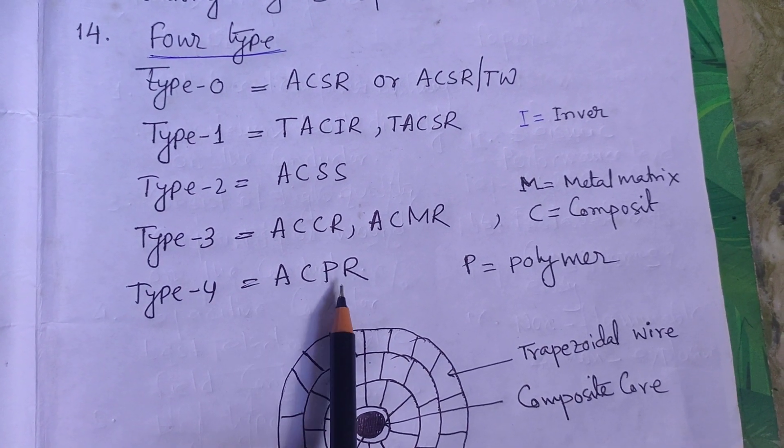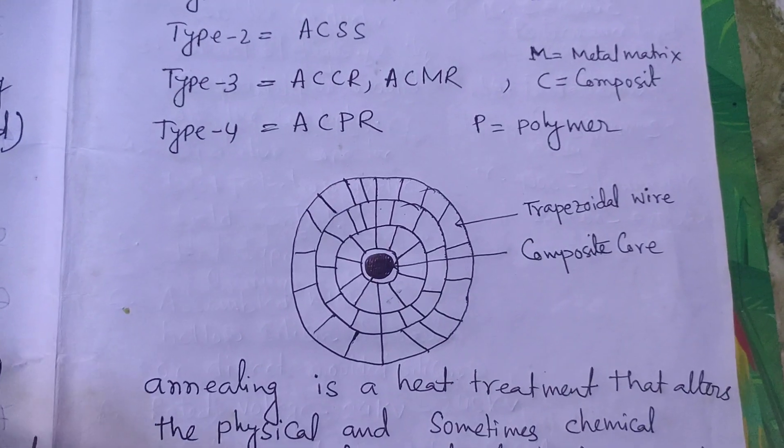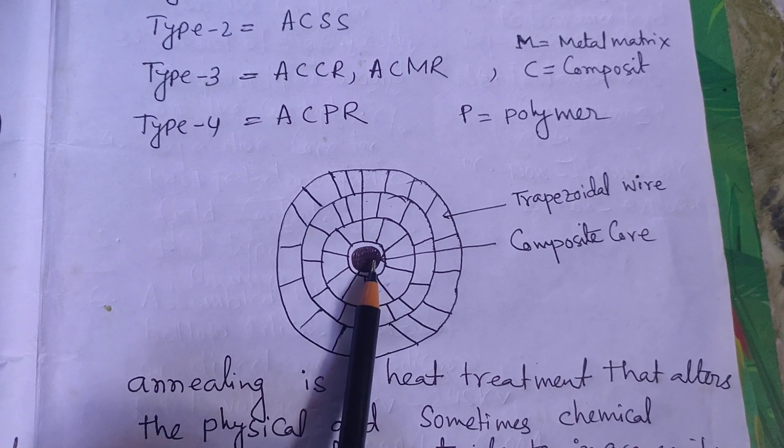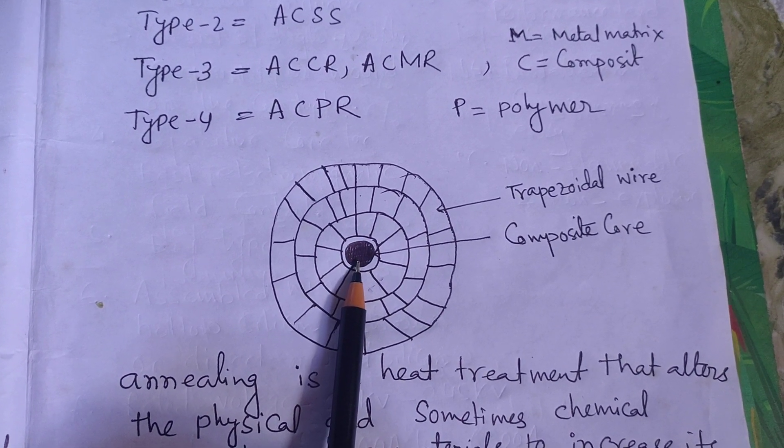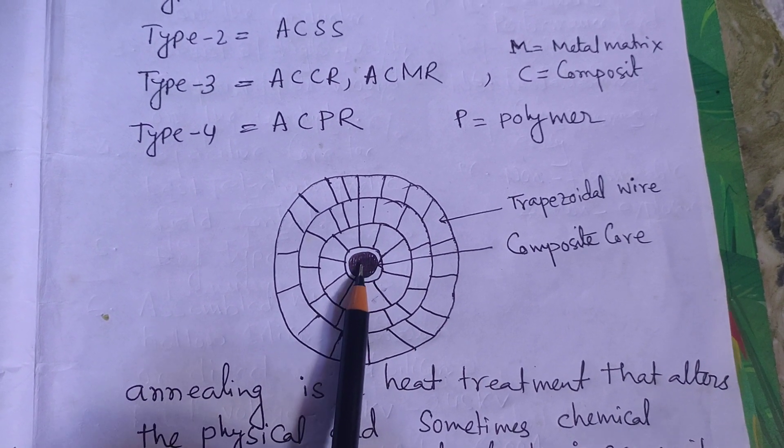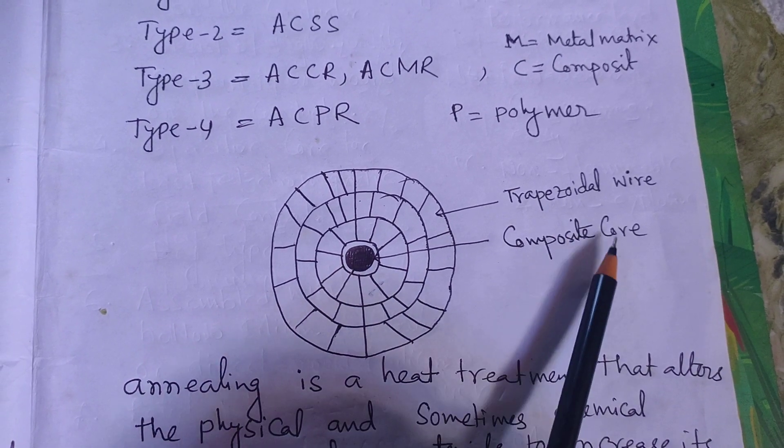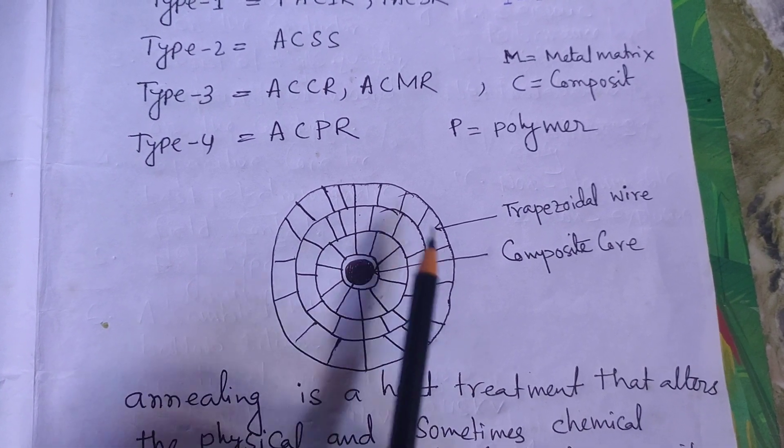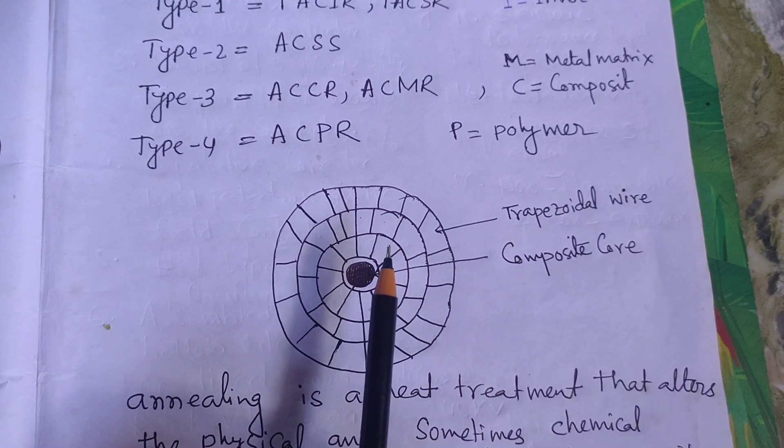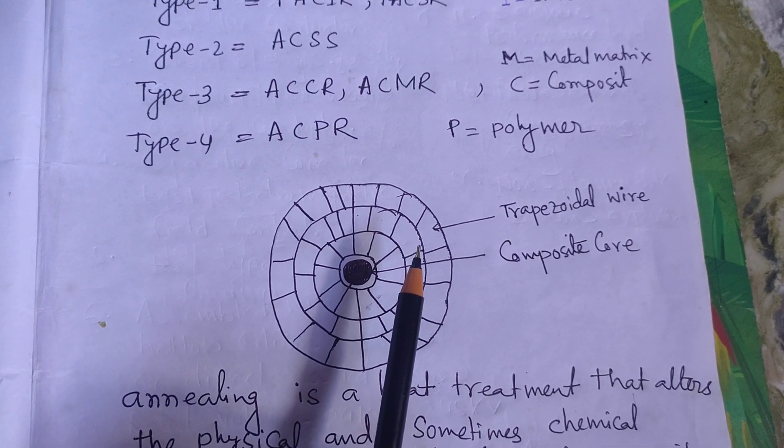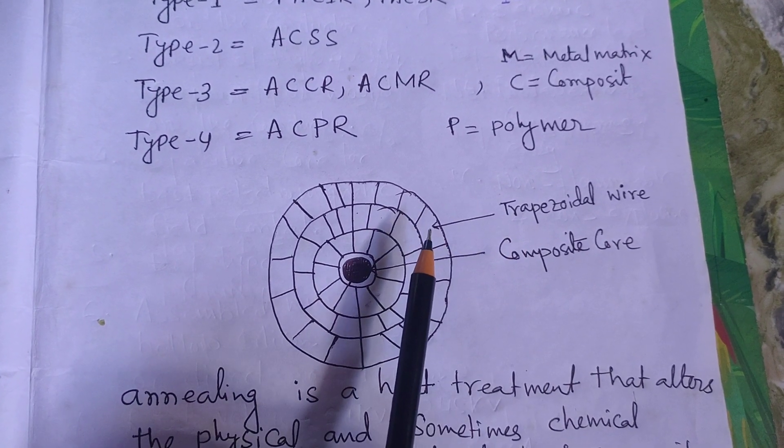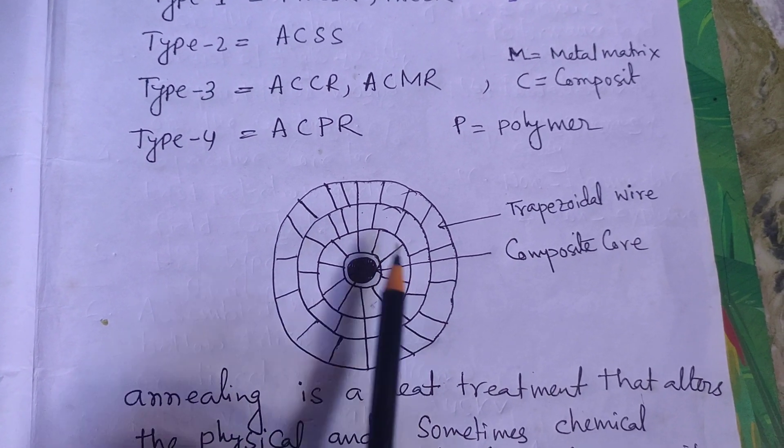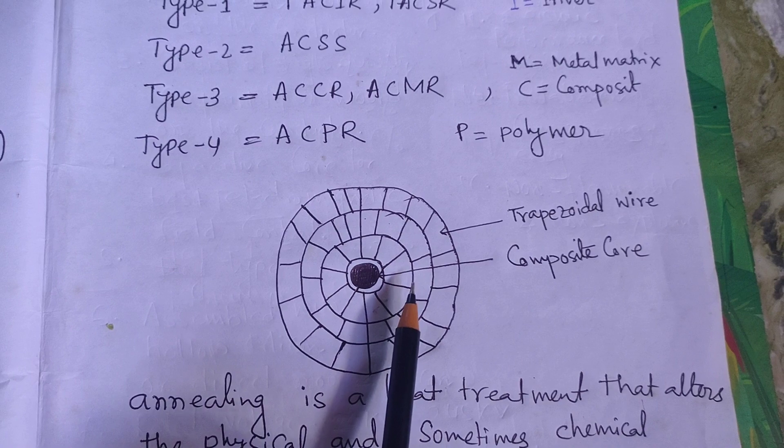A hand sketch drawing of HTLS conductors: Here the composite core is used as the center of the conductor. All the other aluminum wires are annealed aluminum. The shape is trapezoidal. The first layer has 1, 2, 3, 4, 5 - 10 conductors.